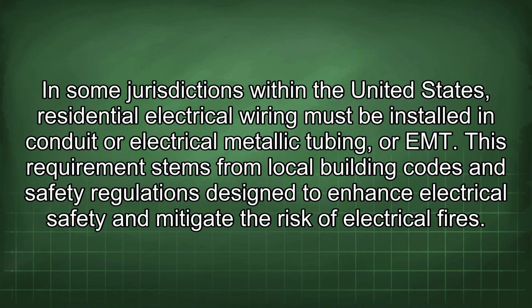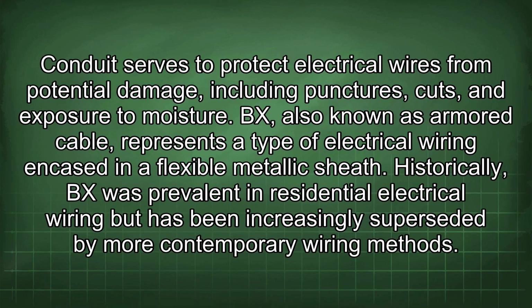In some jurisdictions within the United States, residential electrical wiring must be installed in conduit or electrical metallic tubing, or EMT. This requirement stems from local building codes and safety regulations designed to enhance electrical safety and mitigate the risk of electrical fires. Conduit serves to protect electrical wires from potential damage, including punctures, cuts, and exposure to moisture.